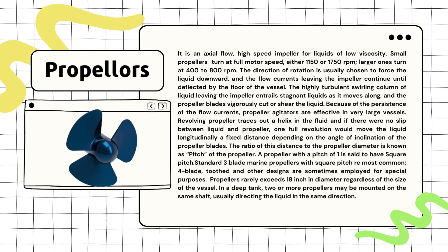A propeller agitator is a device used to mix liquids, especially those with low thickness. It works by spinning small propellers very quickly, at around 1150 to 1750 RPM for smaller ones and around 400 to 800 RPM for larger ones. The propeller usually spins in a way that pushes the liquid downward.